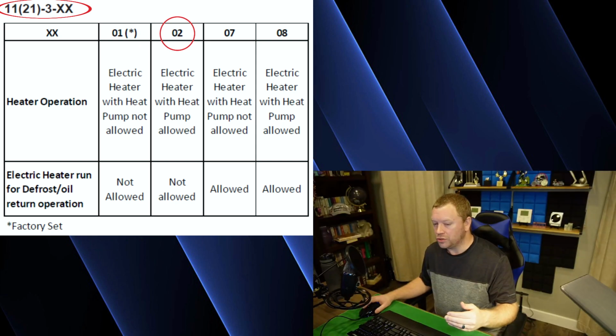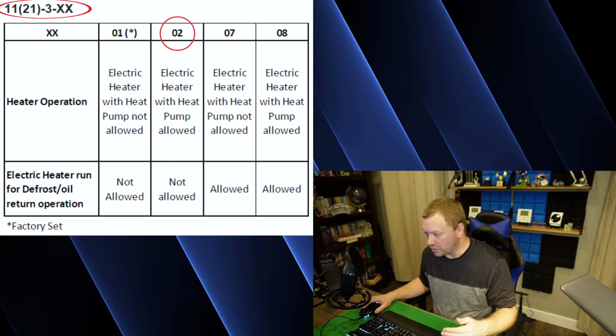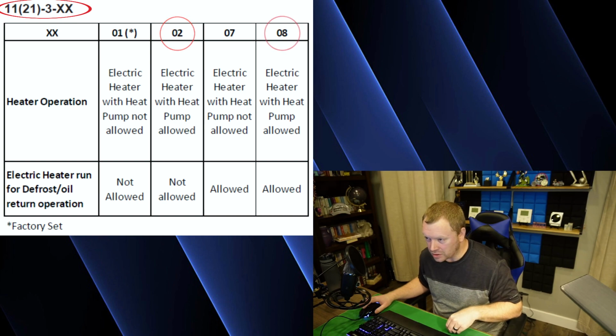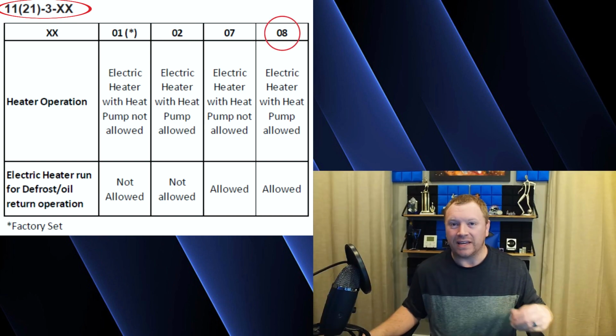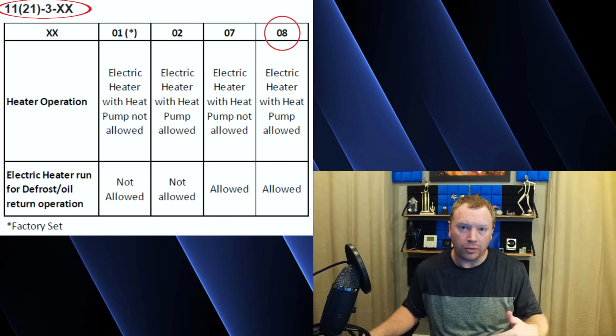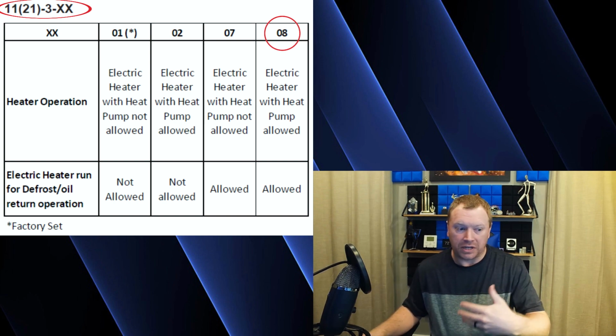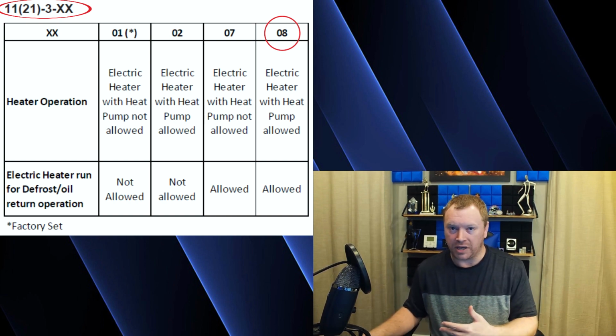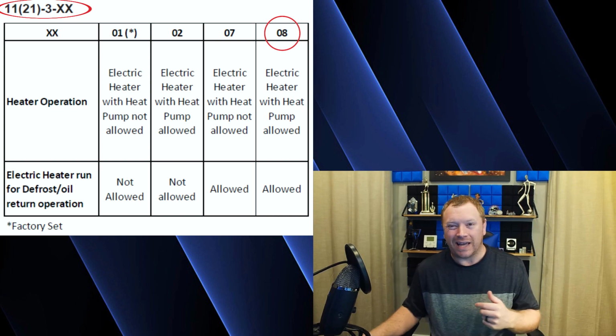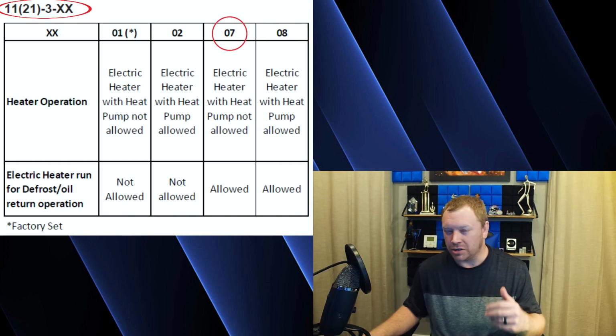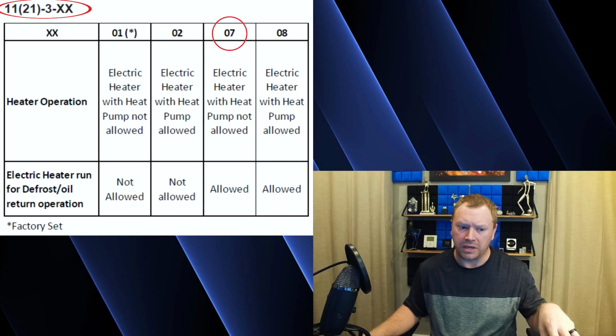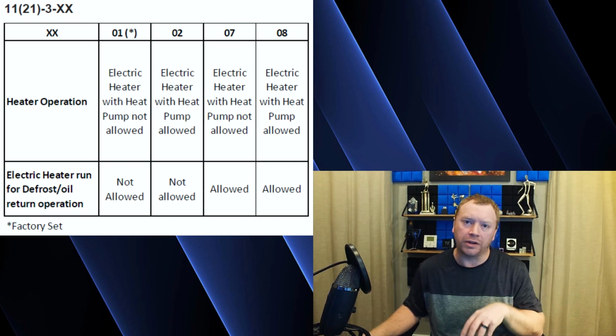Now, if you want to allow the strip heat to run with the heat pump and run with defrost, then you would set mode 21, setting 3-01 to 3-08, enabling the strip heat for both defrost and simultaneously heating with the heat pump to help it catch up for supplemental purposes. The last setting option is 07.